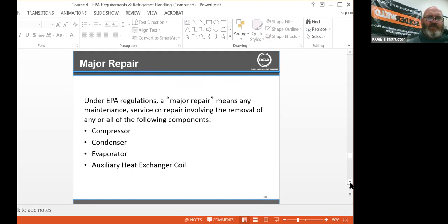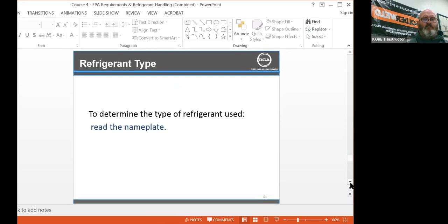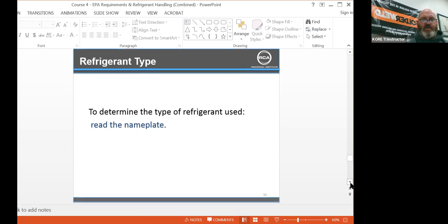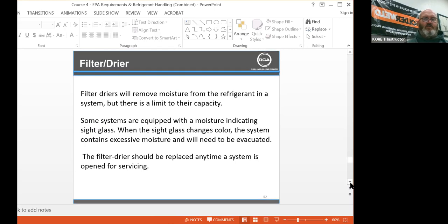Under EPA regulations, a major repair means any maintenance, service, or repair involving the removal of any or all of the components: compressor, condenser, evaporator, auxiliary heat exchanger coil, meaning like a subcooler would be an auxiliary heat exchanger coil. To determine the type of refrigerant used, read the nameplate or your PT pressure temperature chart. Filter dryers will remove moisture from the refrigerant in a system, but there is a limit to their capacity. Some systems are equipped with a moisture indicating sight glass. When the sight glass changes color, the system contains excessive moisture and will need to be evacuated.